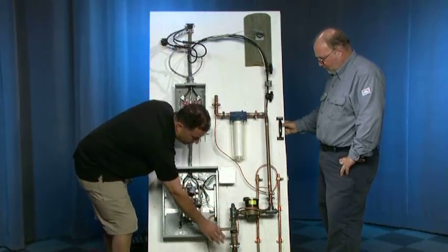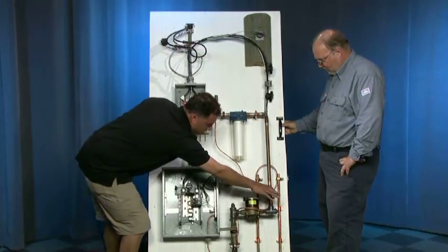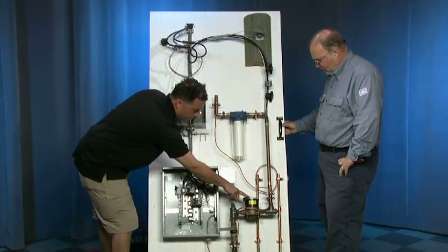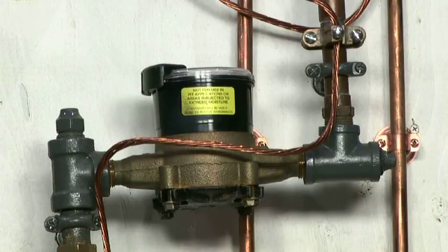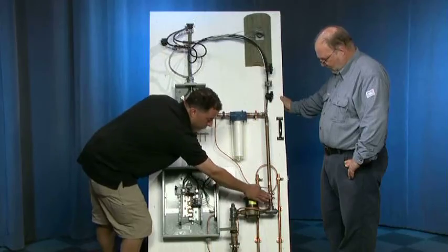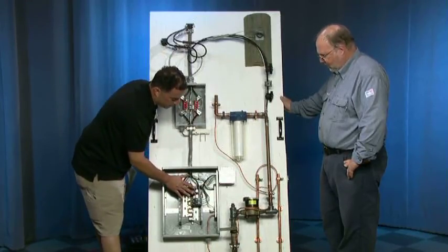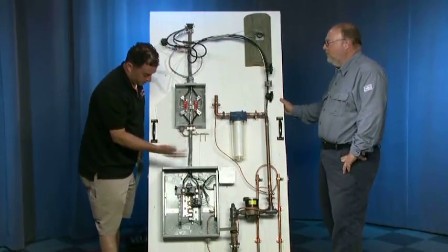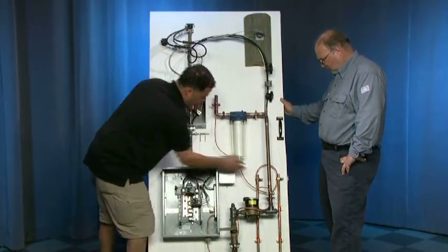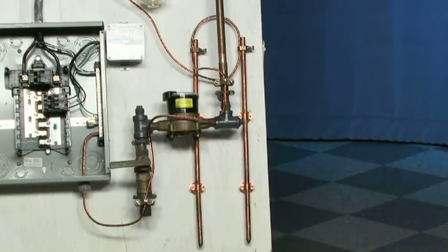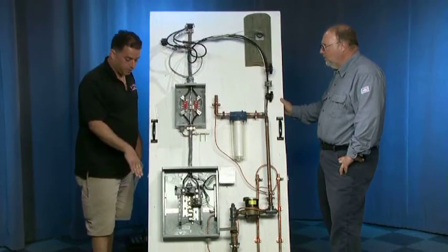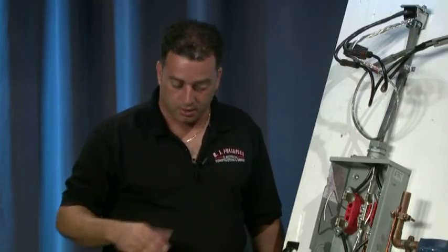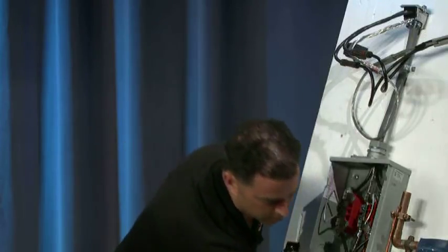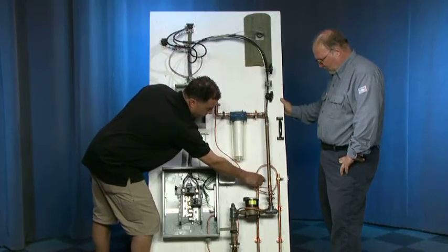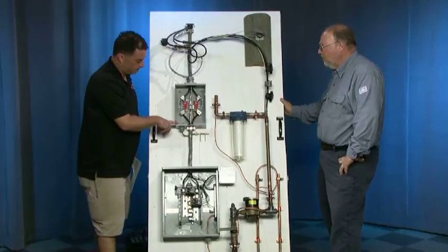This shows the water main being grounded on the line side and the load side, which essentially is just jumping out this meter. And the reason for that is if the water company has to come in and replace, repair, or alter this meter, they're maintaining a good path to ground from your electrical system. Another electrical redundancy backup is your ground rods. These are installed under your meter socket, typically outside of your home. They're 8 feet in length, and we drive them into the ground. They need to be 6 feet apart, and we connect them with a piece of copper, like this shows, and these direct burial rated clamps, and that is connected to your meter socket.